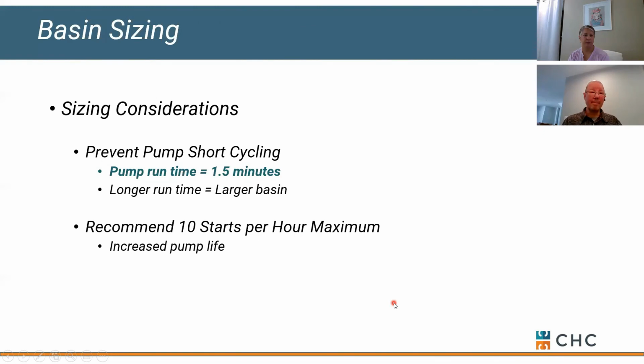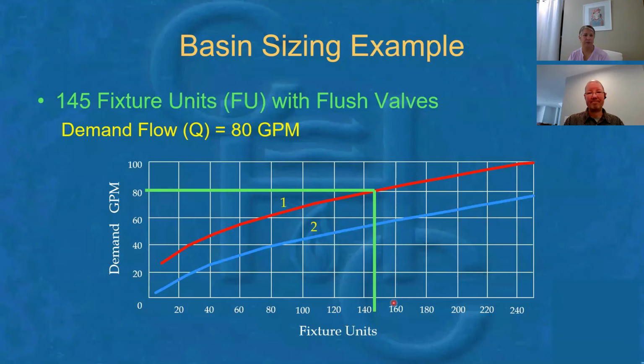Good rules of thumb. Anytime our pump runs, we want it to run for a minute and a half. Not more than 10 times an hour, which is normally why we have redundant pumps in the basin, so they alternate. You don't have one pump running all the time. So we just have to keep those in mind. Let's look at a quick example.